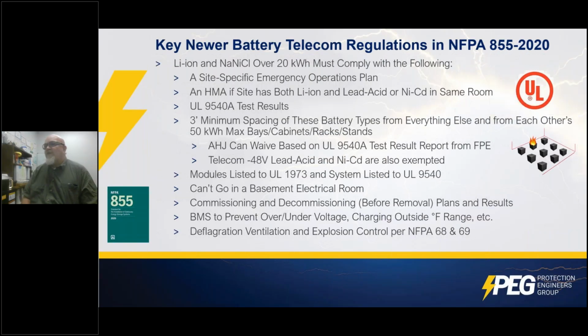Lithium ion and sodium nickel chloride over 20 kilowatt hours have to comply with the following. You have to have a site-specific emergency operations plan. These don't apply to lead acid, but if you mix batteries in the same room, then you have to have a hazard mitigation analysis done by a fire protection engineer. You have to have UL 9540A test results for these modern batteries. That's a large-scale fire test. If you're indoors as opposed to outdoors, you have to put 3-foot minimum spacing between these battery types, or ask the AHJ about 50 kilowatt hour maximum cabinets, stands, whatever.